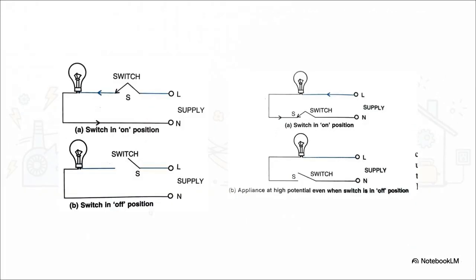The exact same logic applies to your light switches. A switch must always break the live wire. If it's on the neutral wire, flipping the switch will turn the light off, but the entire light fixture is still live, still at a high potential. This is super deceptive and creates a serious shock hazard if you go to, say, change the light bulb.